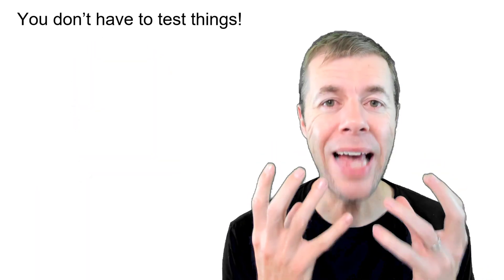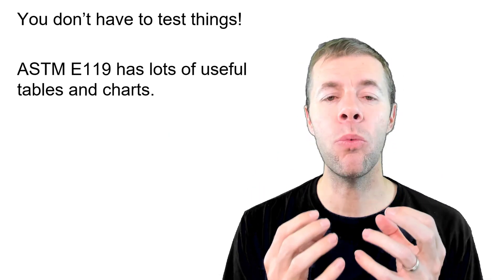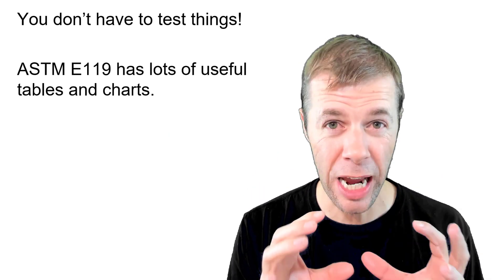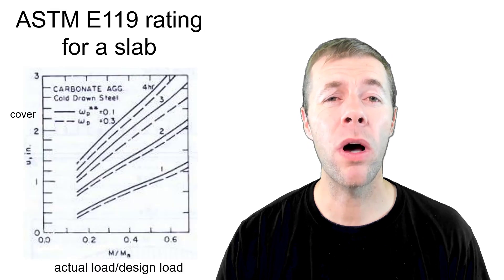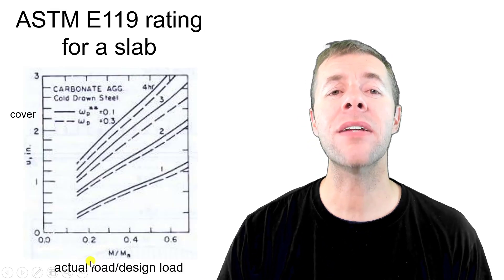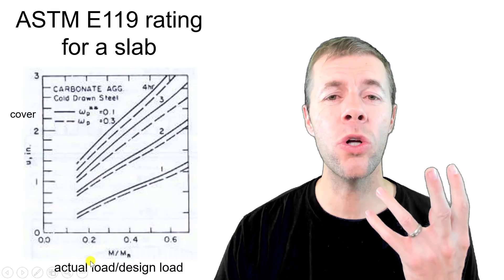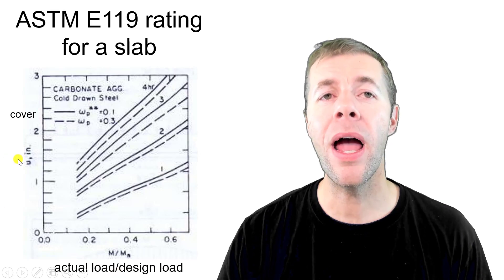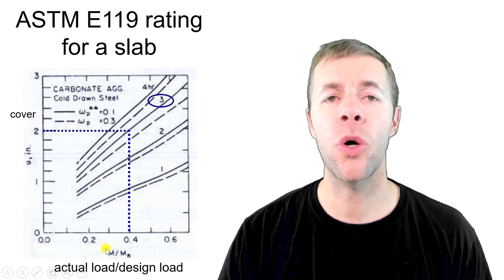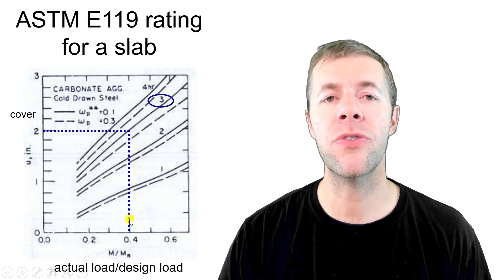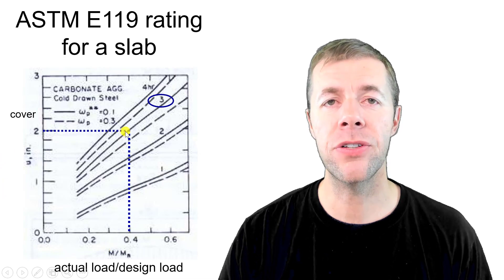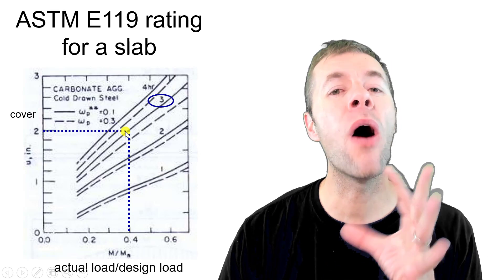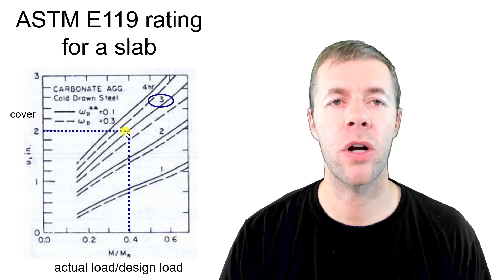But things don't have to be tested. ASTM E-119 has lots of useful tables and charts in it as well. Here's one of them. This shows on the x-axis the actual load on a structure versus the total capacity and on the y-axis the cover. I'm showing two points here. If you come with about this load ratio and this cover, that's about a three hour fire rating for that structure.